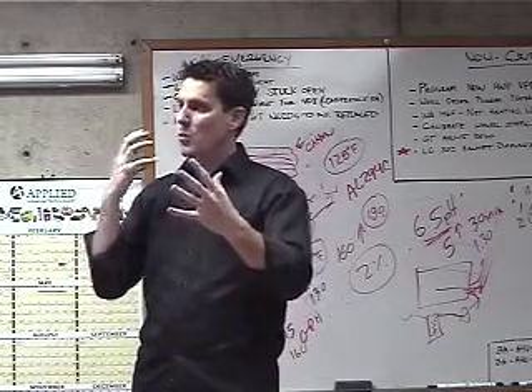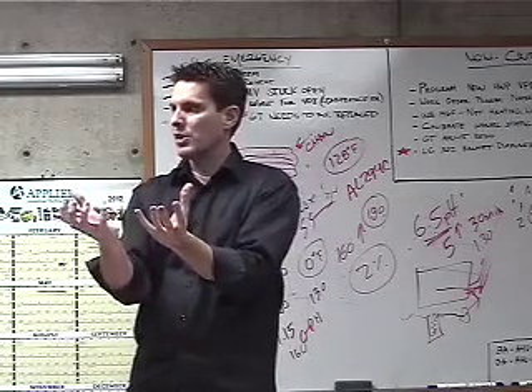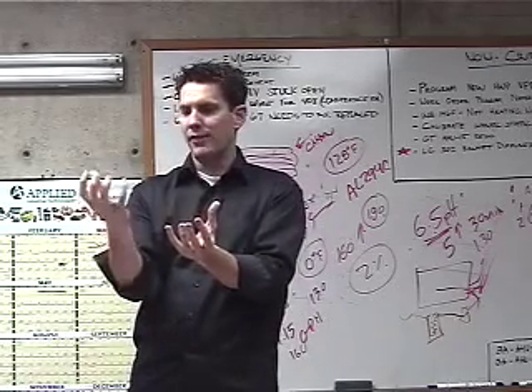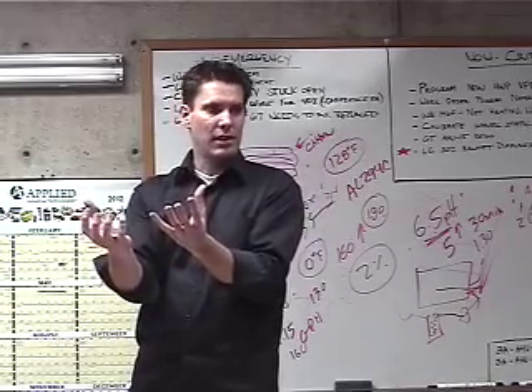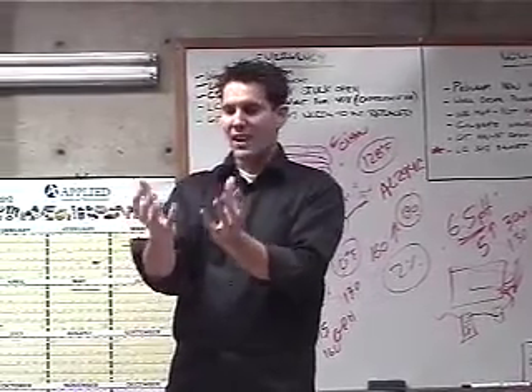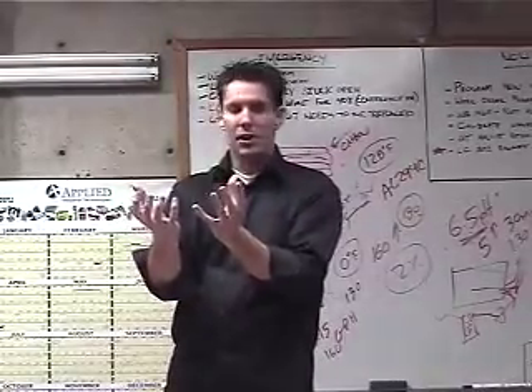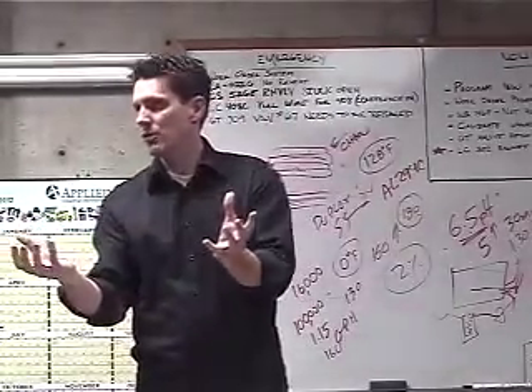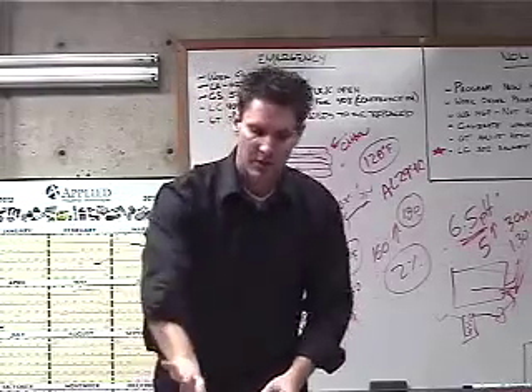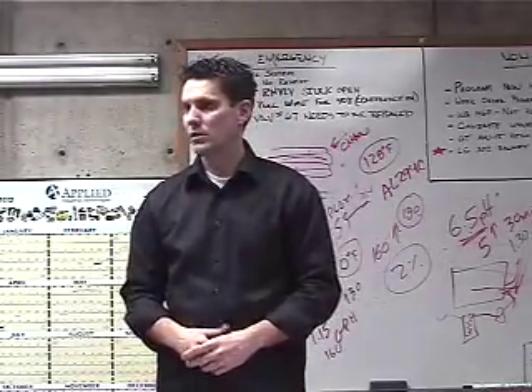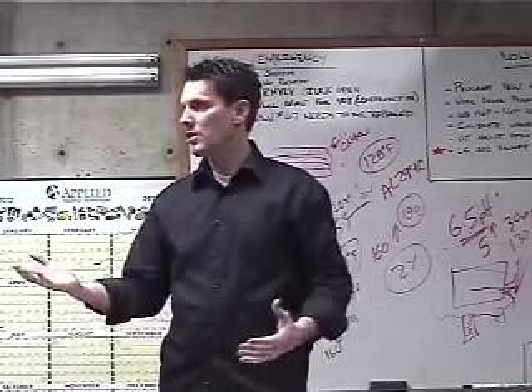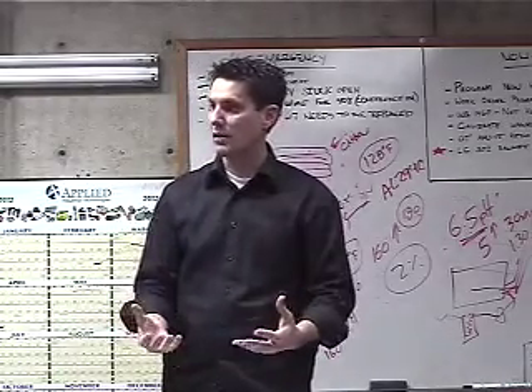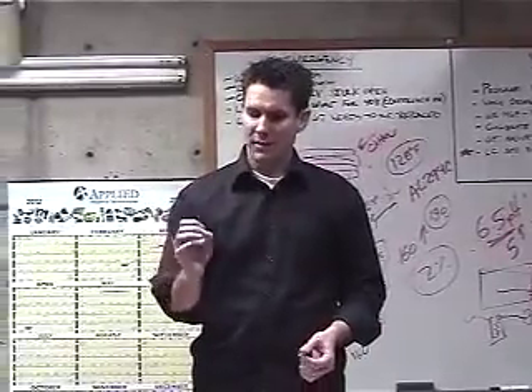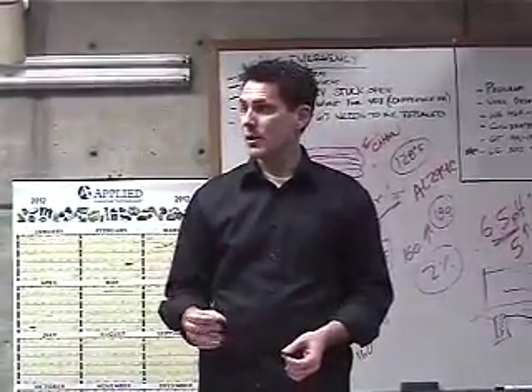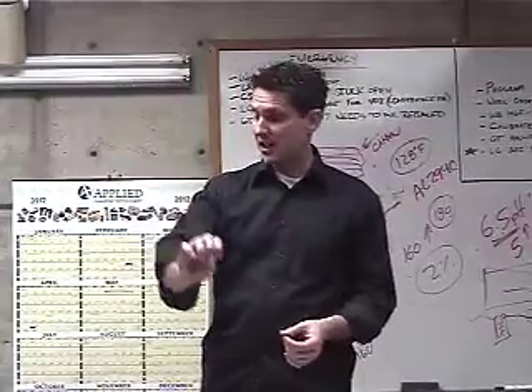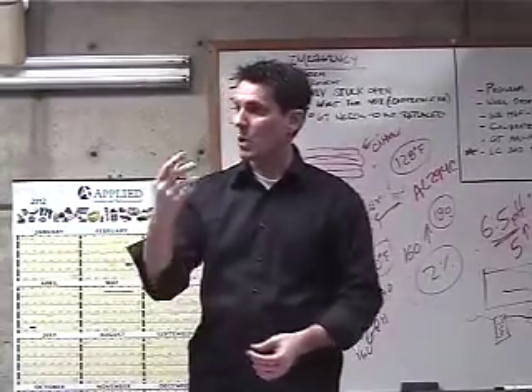What that means is we've dialed in this proper air to fuel ratio, so for every 1 volume of gas, we've got 10 volumes of air, is typically what that works out to be. Okay. Now, if that were to change, then your flame is going to change. I mean, just go back to some real elementary stuff. You have a candle burning and you put a cup over the candle, what happens to the flame? Why? There's no oxygen, it runs out of oxygen. It burns up the oxygen inside and then it runs out. Before it burns out, what does the flame start to do? Starts to what? Smoke? It gets smaller, it changes color. You might get more smoke off of that.